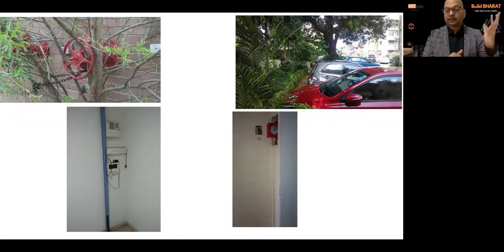You see an extinguisher, a fire alarm panel that is not accessible, not even connected, not even charged, without batteries. A hydrant you need to find behind the trees. An extinguisher you need to find behind the table. A manual call point you can't even operate. People don't know what this break glass is, and the glass is almost broken. Walls have been closed up with sprinkler systems attached, and they are kept closed with no water inside.